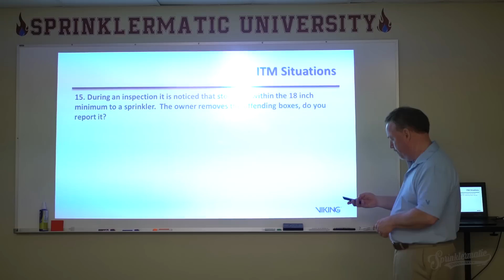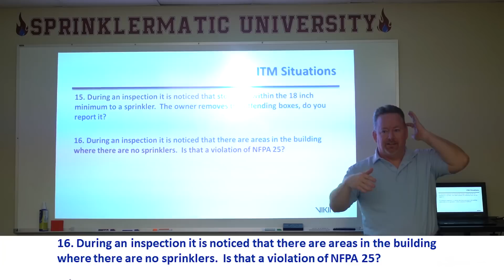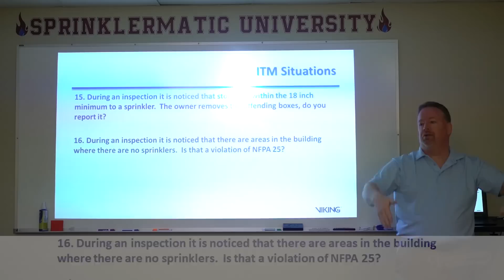How about this? During an inspection, it is noticed that there are areas in the building where there are no sprinklers. Is this a violation of NFPA 25? So you walk in, you go down this corridor here, and there's been some renovation in the building. It's an older building. All of a sudden they're putting loft apartments in or something like that. It has a sprinkler system up above, but they've created this corridor in here, and they didn't drop sprinklers down into it. And now as the inspection technician, you're going through filling out your forms in NFPA 25, and you're saying, there's no sprinklers here. So what do you think? Is that a violation of NFPA 25?